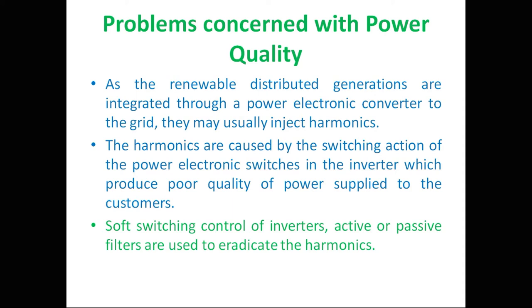The main reason for harmonic injection is the switching action of power electronic switches in the inverter, which produces poor quality of power supplied to customers. The solution is soft switching control of inverters, or the use of active or passive filters to eradicate harmonics. There are many methods under each of these approaches.